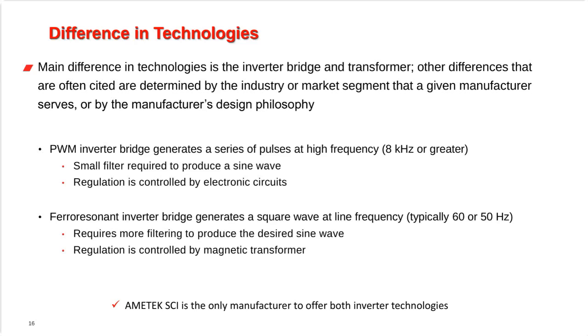The transformer is a constant voltage transformer. So the inherent properties of the ferro-resonant transformer limit the voltage of the output of that transformer. It is the transformer that does that. There's no controls in the inverter that does that.